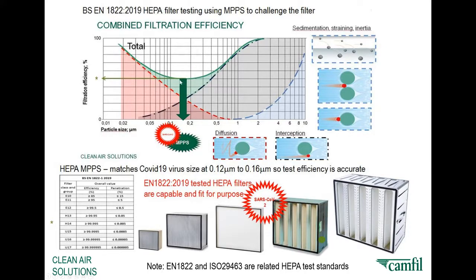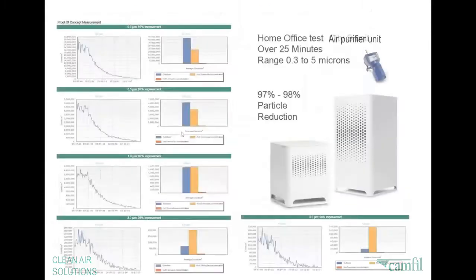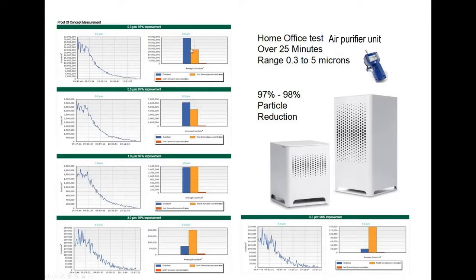So most penetrating particle size, that would be, for example, for an H14 commonly found in air purifiers, 99.995% removal efficiency at 0.12 to 0.16, which is the virus particle size for COVID-19. So that's an extremely effective solution. So standalone air purifiers will deliver in an extremely short period of time. This is a particle count showing the reduction over a 25-minute period. So 0.3 microns goes from about 30 million particles per cubic meter down to a couple of 100,000 over that period of time.